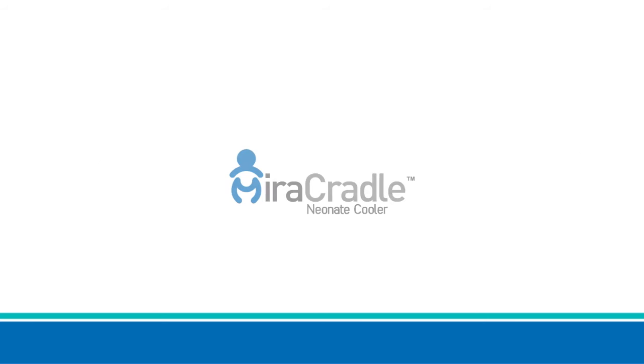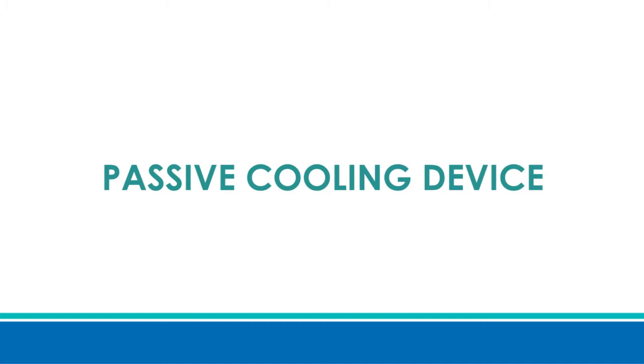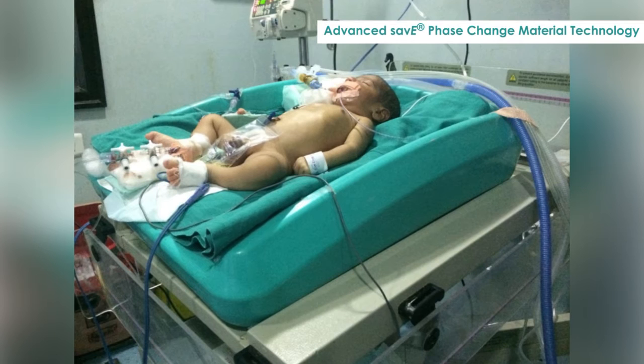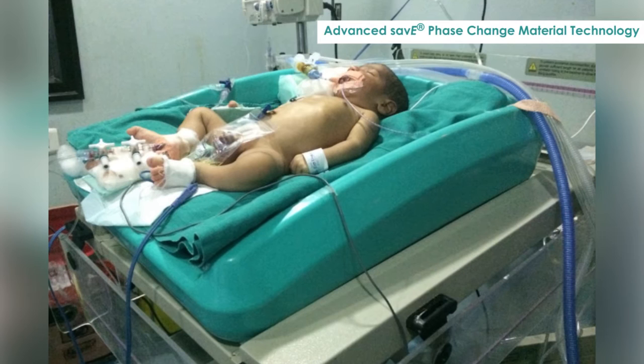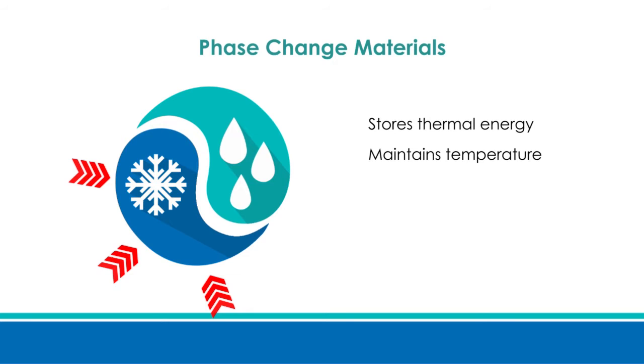MiraCradle Neonate Cooler is a passive cooling device for newborns suffering from HIE. It uses the advanced Save phase change material technology to give precise temperature control of 33 to 34 degrees centigrade for a period of 72 hours, with minimal manual supervision and no requirement of constant electricity supply. Phase change materials are special thermal energy storage materials that store or release large amounts of thermal energy at a particular temperature while changing phase from solid to liquid or liquid to solid.